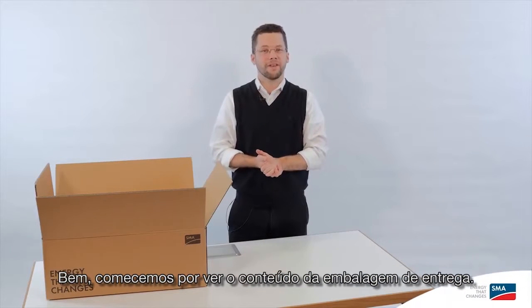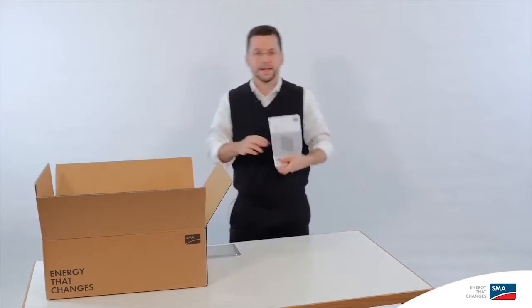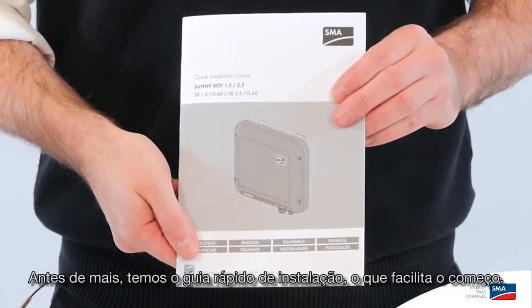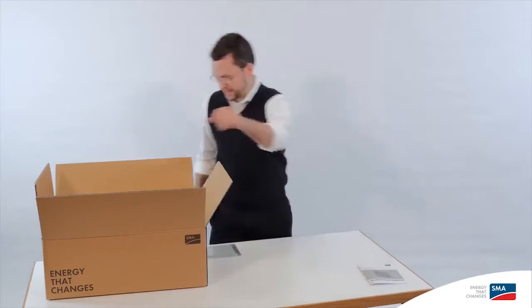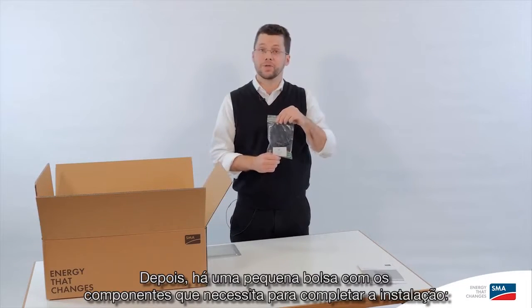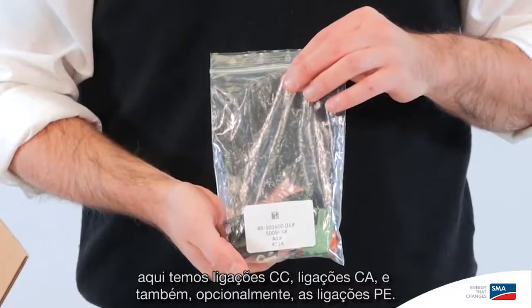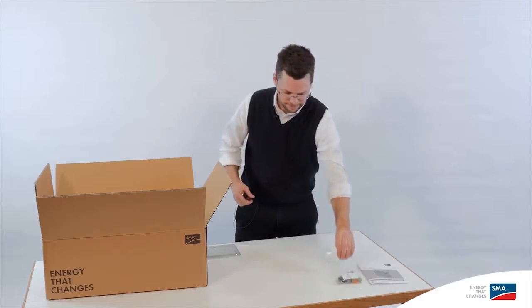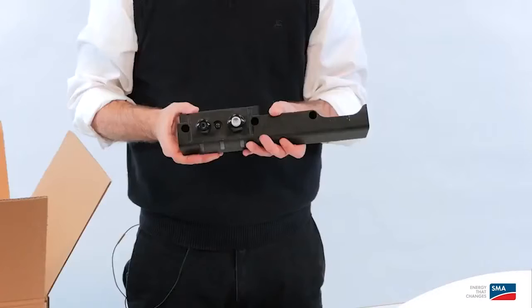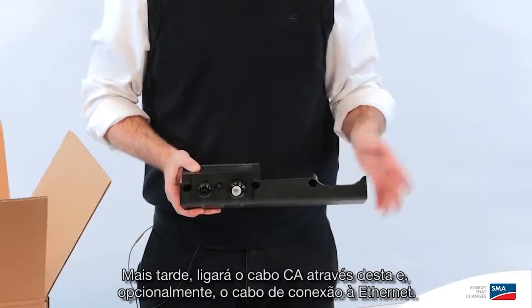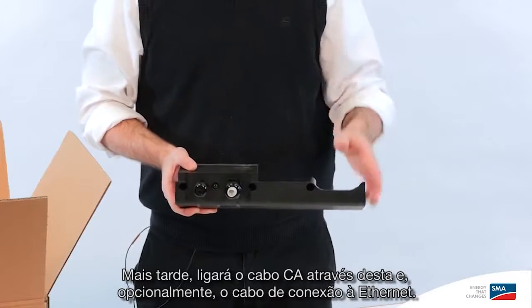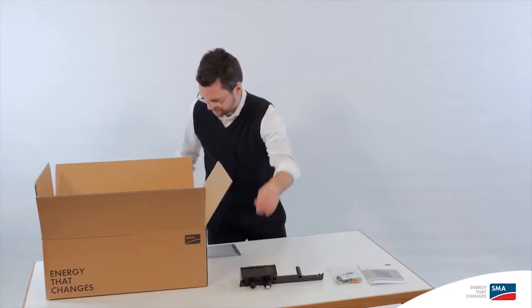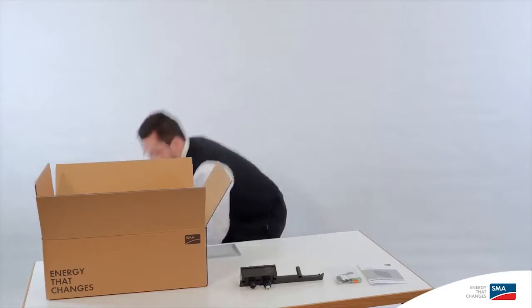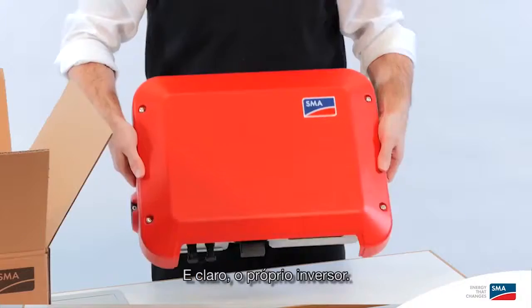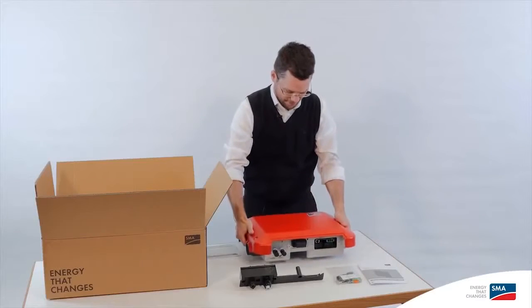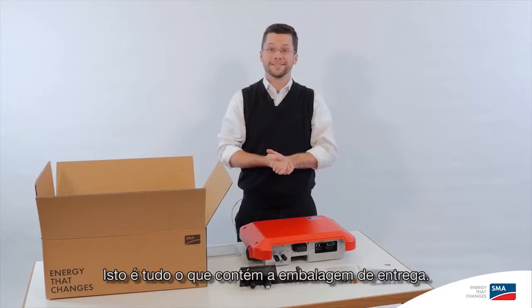Let's start by taking a look at what's included in the scope of delivery. First, there's the quick installation guide, which makes it easy to get started. Then there's a bag of parts needed for installation: DC connections, AC connections, and optionally the PE connection. Here's the cover of the inverter—later you'll feed the AC cable through this, and optionally the Ethernet connection cable. And of course, the inverter itself. That's everything included.